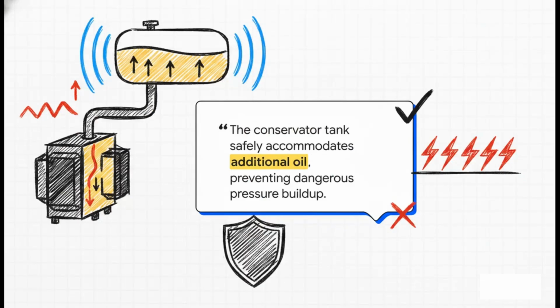The engineering guidelines hit the nail on the head here. They state that as transformer temperature increases, insulating mineral oil expands in volume, and the conservator tank safely accommodates the additional oil, preventing dangerous pressure buildup. So the crucial takeaway is that the conservator tank isn't just some random accessory up there. It is the ultimate safety net. It's an expansion chamber specifically designed to handle this massive volumetric expansion smoothly and safely.